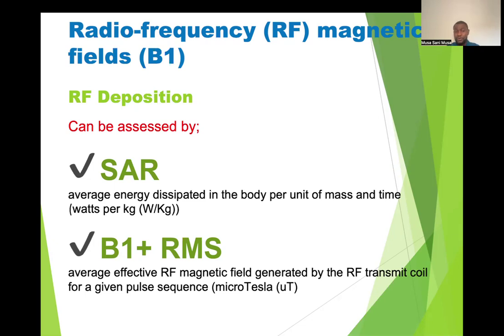As a result, what could potentially happen is what we call RF burns. So it's really important to get the patient's weight and height so that the MRI scanner can calculate the appropriate specific absorption rate. And with regards to B1 root mean square, which is an average effective RF calculated within the duration of the scan.